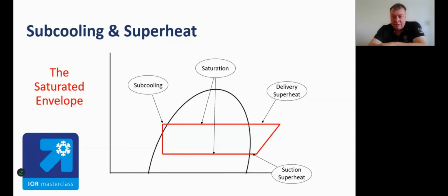Okay, on the right-hand side of the envelope, we've got the suction superheat, then the compression. At the top, we have delivery superheat, back through saturation, and then out the other side. Hopefully, if we've got a healthy system, we've got a little bit of natural subcooling that I'll come on to, through the expansion valve, and it drops back into the saturated envelope.